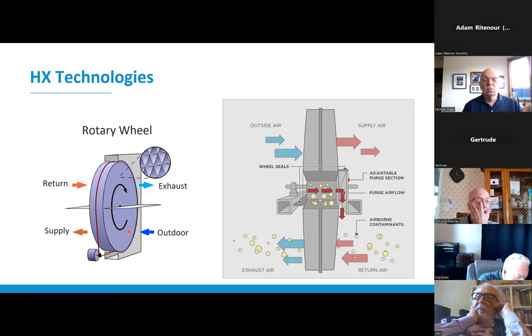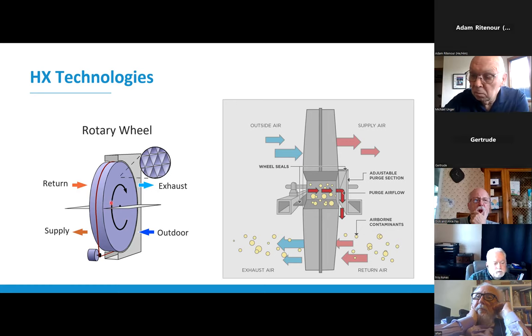So the way this works is, imagine this wheel spinning, and while it's in the upper hemisphere, you've got the return air coming through those microchannels, warming up this aluminum, and that exhaust air is going out colder than when it entered the wheel. And then as the wheel keeps turning and it's now going into the lower hemisphere, the outdoor air is going through those same channels, picking up that heat and supplying pre-warmed outdoor air to the building.